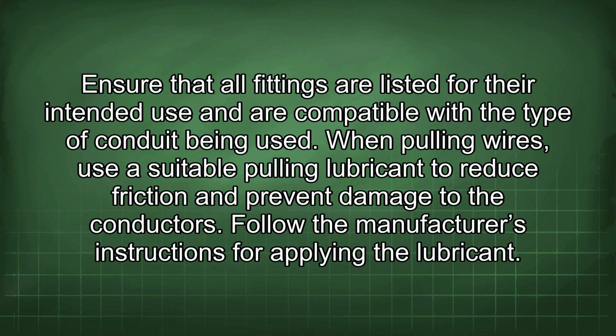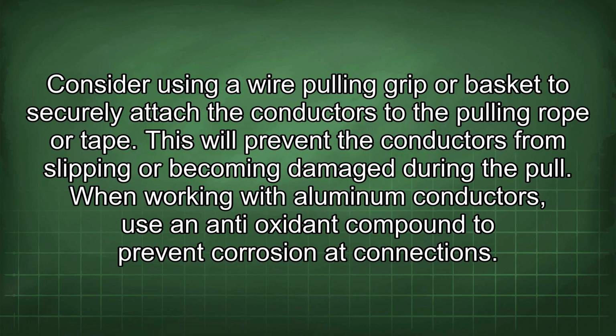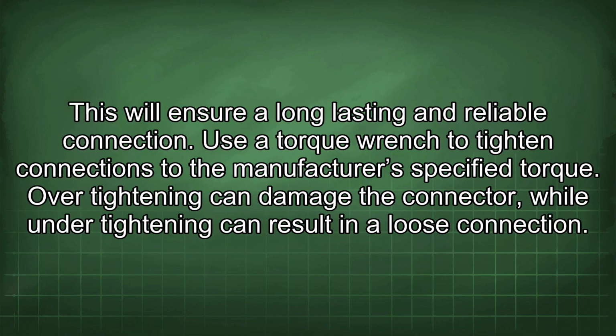When pulling wires, use a suitable pulling lubricant to reduce friction and prevent damage to the conductors. Follow the manufacturer's instructions for applying the lubricant. Consider using a wire pulling grip or basket to securely attach the conductors to the pulling rope or tape. This will prevent the conductors from slipping or becoming damaged during the pull. When working with aluminum conductors, use an antioxidant compound to prevent corrosion at connections. This will ensure a long-lasting and reliable connection.